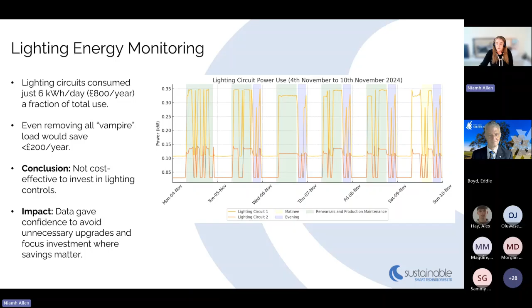This is another example. Again, a theatre company wanted to look at lighting controls for the theatre - is it worth it? So we put some CT clamps on the lighting circuit and monitored it. It would cost them £800 a year, and we found about £200 of vampire load, lighting running when it shouldn't be. It wasn't cost effective for them to invest, so they didn't do it - they moved on to the next thing. It's about making sure the business case stacks up when you're looking at interventions.